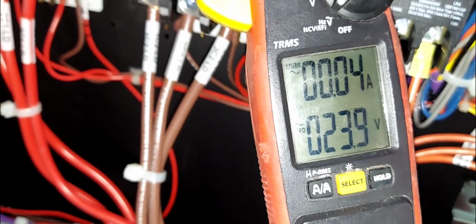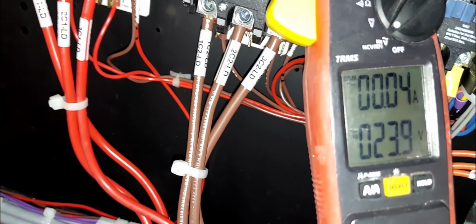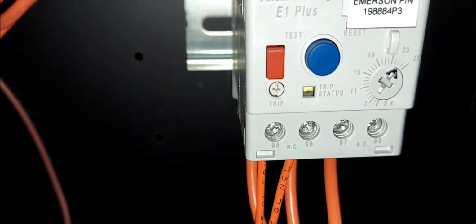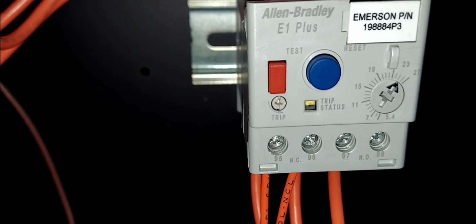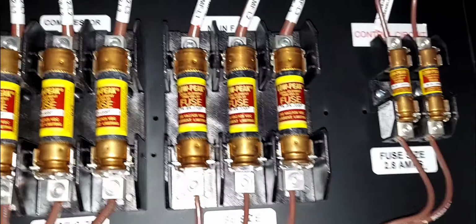Okay, so I'm gonna go first. I'm gonna check my contacts on the overload. And you can see that I'm reading 239 volts potential across the contacts. So these are open for certain. And these are supposed to be normally closed, or NC, as you can see right there. NC, baby.